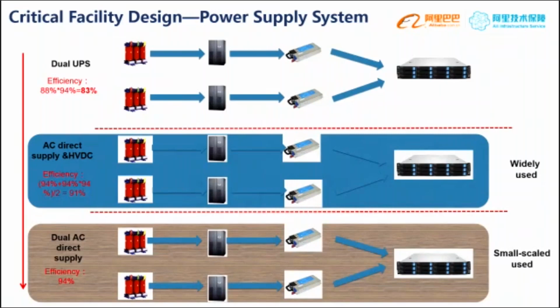You may say UPS has an eco mode, but that's a different topic. High voltage DC is online, but UPS eco mode is offline. This system is more reliable than the UPS system because the battery is connected to direct current.